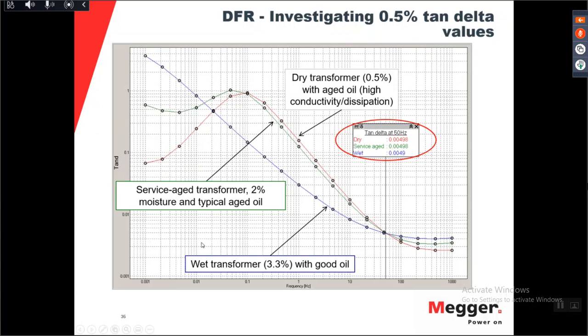If you instead look at the very wet transformer, which has very, very, very high moisture content in the paper, but it has a very good oil, you can see that in the higher frequency range, the power factor is high. Also in the lower frequency range, the power factor, or the tan delta, is very high. While for a normally service aged transformer, the moisture content... here. This is bad oil, this is good oil.